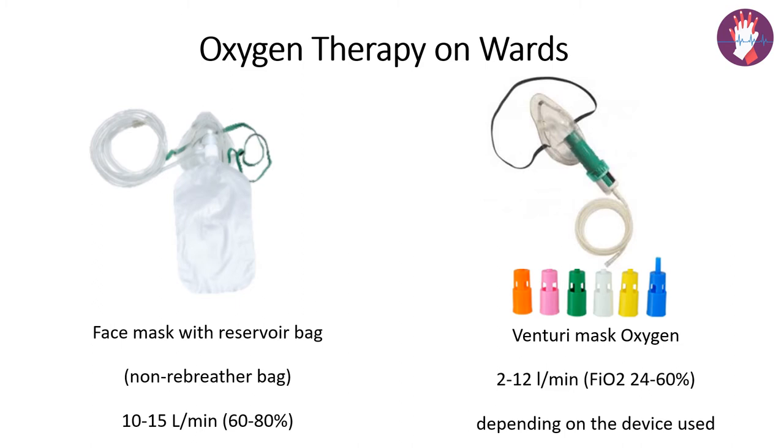The next device is the Venturi mask, which is a high flow mask that adapts the Bernoulli principle. Oxygen passes through a small constricted opening and entrains air from outside, delivering a larger total flow rate to the patient. The size of the constriction determines the flow rate. The masks are color coded, with each color indicating a different flow rate and FiO2, as labeled on the mask. Flow ranges from 2 to 12 liters per minute, and FiO2 can range from 24 to 60% depending on which mask is used.